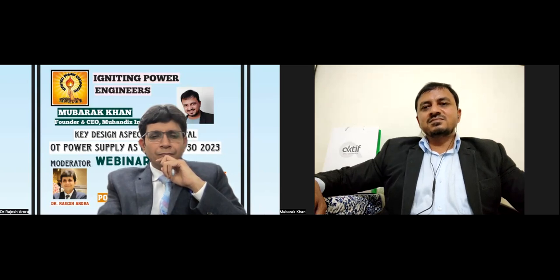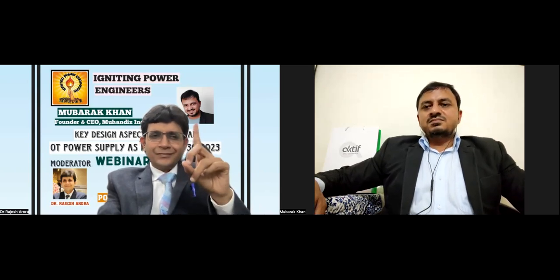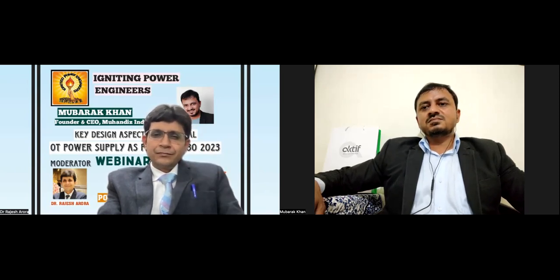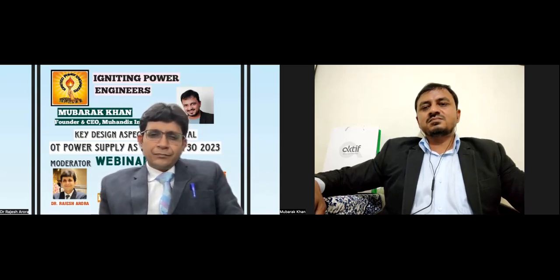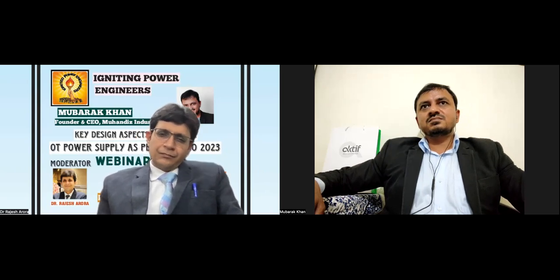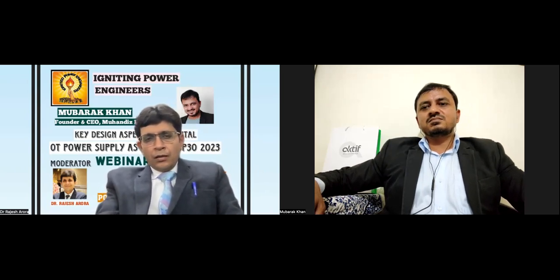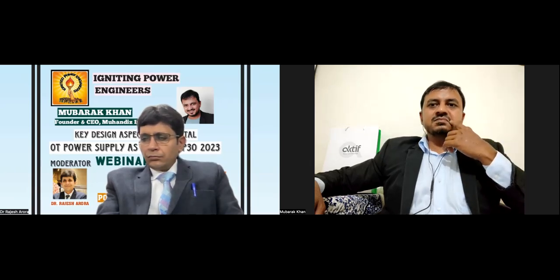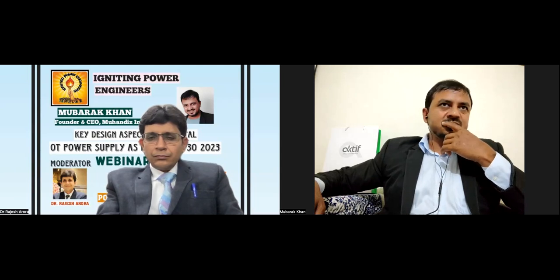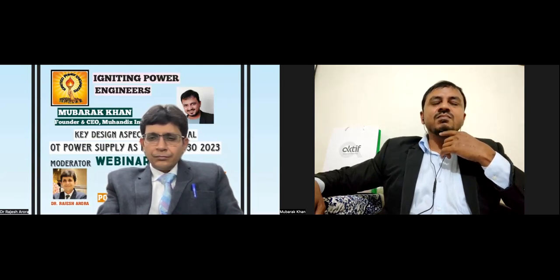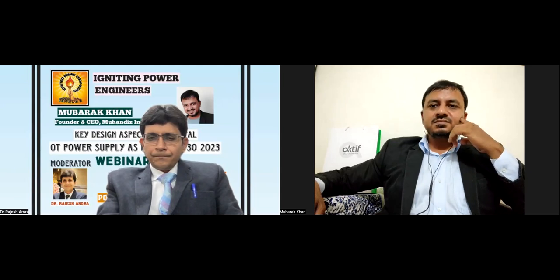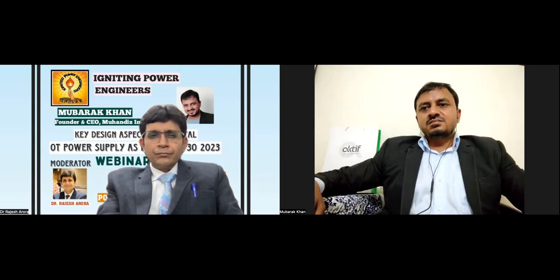Actually, on the panel it was written that the panel supports 10 kVA for single phase. So, are these panels directly connected to single phase, or do we need a 3-phase to single phase transformer in between that would provide that much power? I have very limited knowledge in electrical distribution. I have heard that the maximum we can do is around 6 to 7 kilowatt per phase. So if anyone is drawing 10 kilowatt, is it good to do that on single phase?